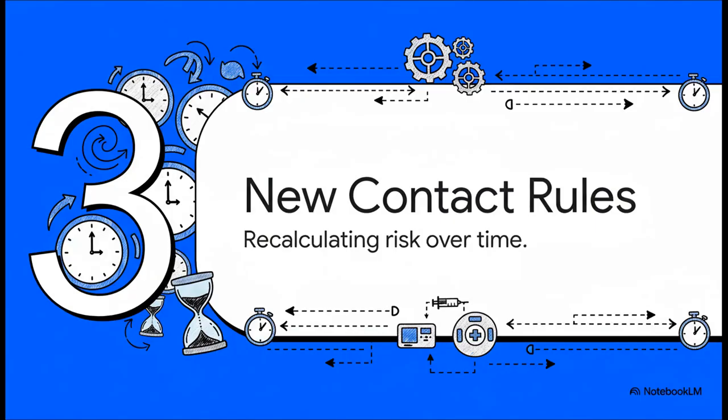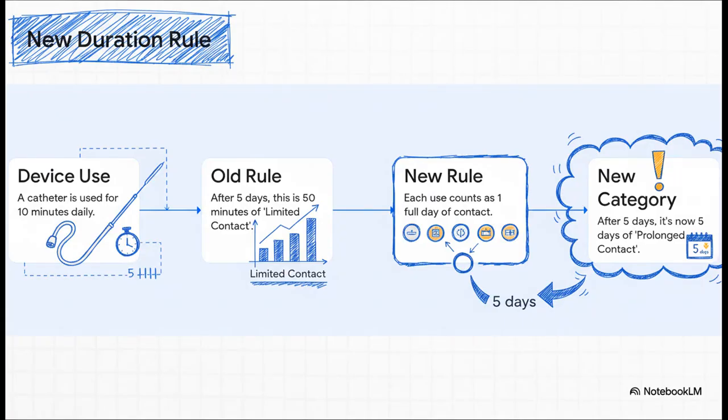Okay, next up, let's talk about time. Because the way we calculate contact duration is being completely overhauled. And trust me, this has massive, massive implications for how devices get categorized and what tests they'll need. Just look at this example. It's so clear. Under the old rules, if you used a catheter for 10 minutes a day for five days, well, that's 50 minutes total. Simple. Limited contact.